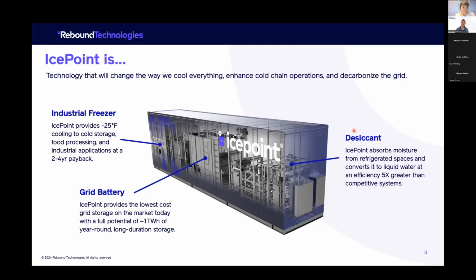A secondary driver the customer is really interested in is the desiccant property of our system. We use brine and ice as our refrigerants, which I'll get to later, and that allows us to simultaneously provide cooling and moisture management. At facilities throughout the cold chain, moisture control is really important.